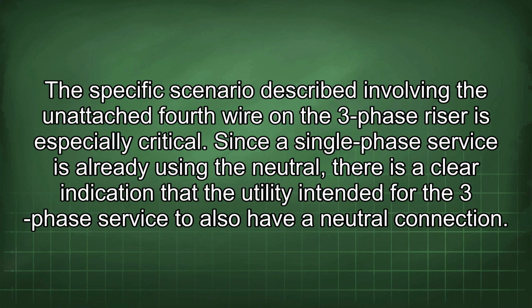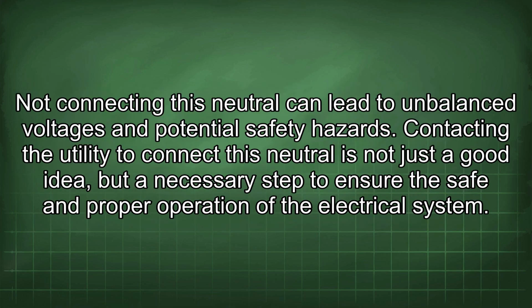The specific scenario described involving the unattached fourth wire on the three-phase riser is especially critical. Since a single-phase service is already using the neutral, there is a clear indication that the utility intended for the three-phase service to also have a neutral connection. Not connecting this neutral can lead to unbalanced voltages and potential safety hazards. Contacting the utility to connect this neutral is not just a good idea, but a necessary step to ensure the safe and proper operation of the electrical system.